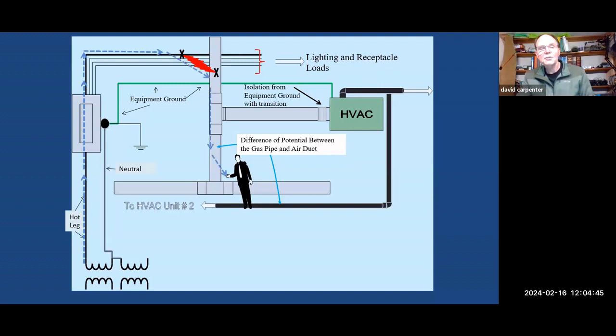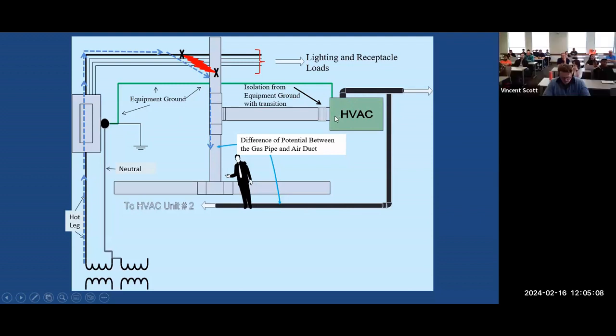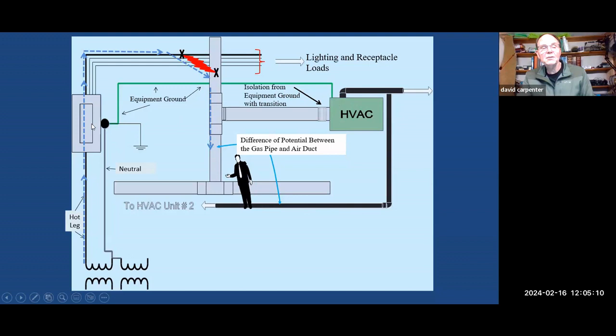This is just the path the energy went through him. The ductwork is where the fault was occurring, where the cable was laying on the duct. You can see the energy going through there, and all he's done is completed the path through the gas piping to the HVAC unit. He's simply bypassed all of the HVAC, and it went through him before it could ever get to the panel board where the breaker was sitting.